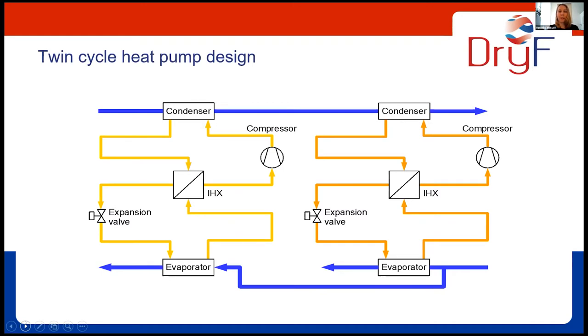In each cycle, we have a compressor module that consists of either a single screw compressor or four piston compressors. Within the refrigerant cycle, we also have an internal heat exchanger, called IHX in this diagram. We need that internal heat exchanger to ensure that we have enough superheat for compression. This is due to the properties of the refrigerant, the shape of the vapor dome, basically, so that we need a large amount of superheat. The internal heat exchanger is a way to provide the superheat in a very efficient manner. We transfer the heat at the outlet of the condenser to the outlet of the evaporator, so we can get the superheat without lowering the evaporation temperature. This is a very brief introduction to the inside of the closed loop heat pump. And with that, I will hand over to Michael.